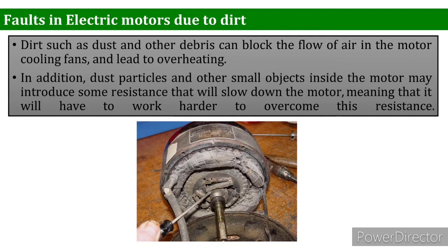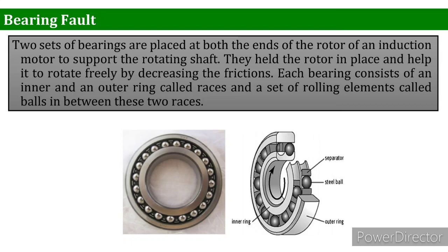And in our previous lecture we studied the mechanical life of the motor; timely care will increase it. So remember, we cannot avoid degradation fully, but we can take care of these motors to avoid further degradation. Now the bearing fault is one of the most important and most discussed mechanical problems in motors and generators. Two sets of bearings are placed at both ends of the rotor of the induction motor to support the rotating shaft.